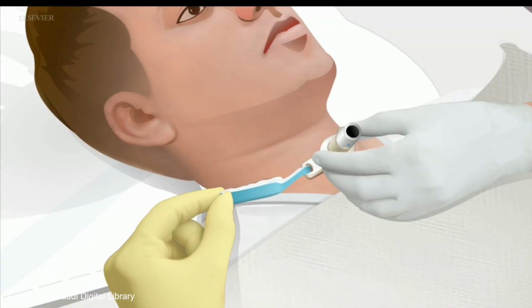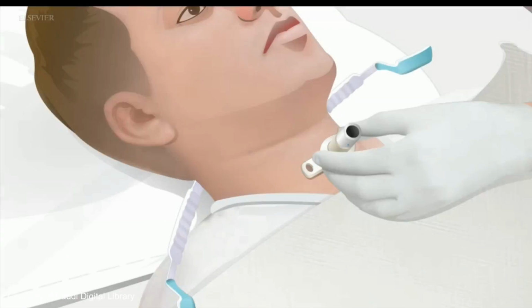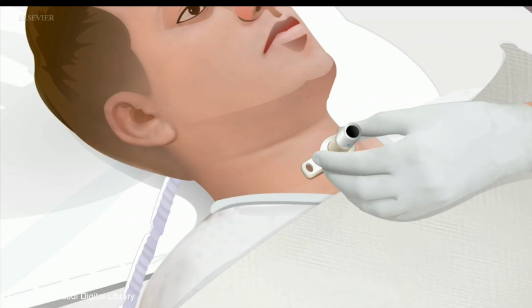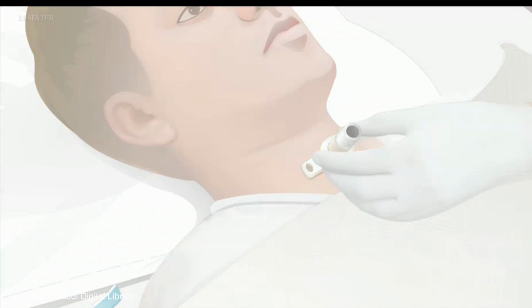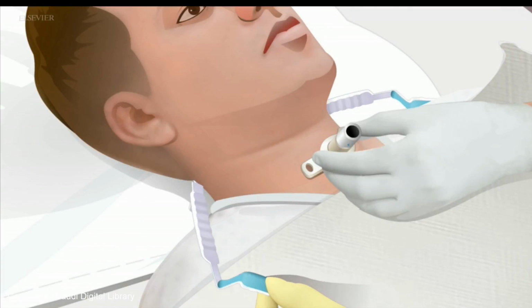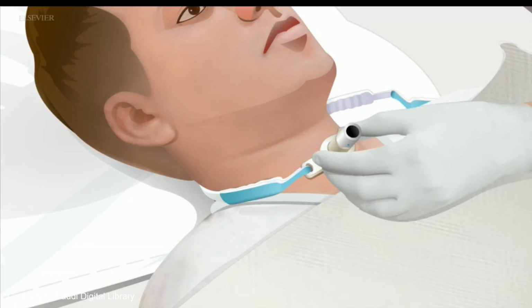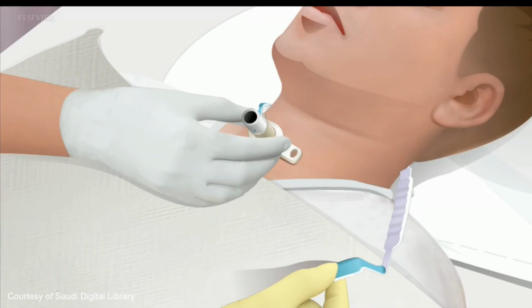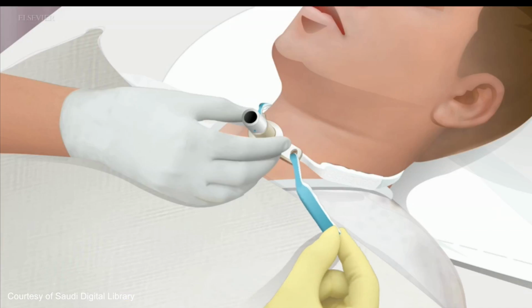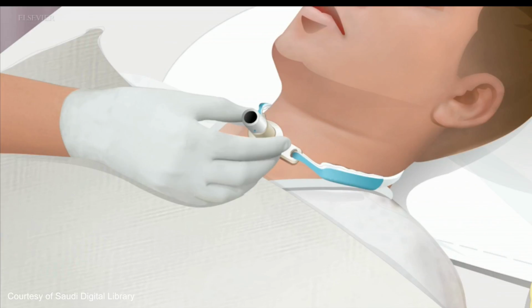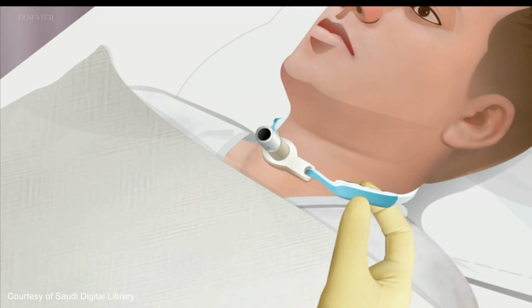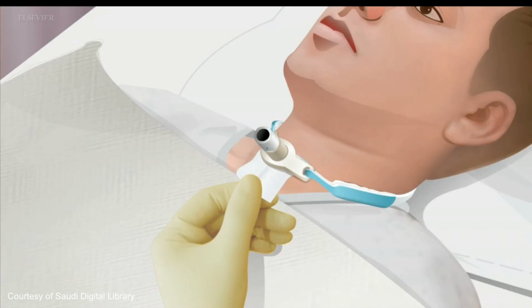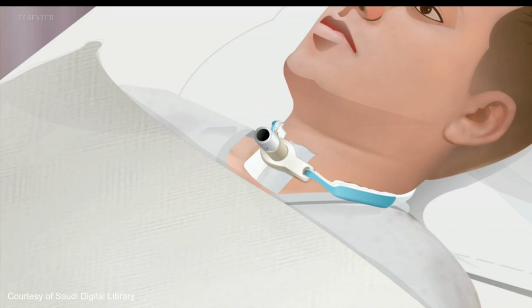Secure tube, tracheostomy tube holder. Instruct the assistant, if available, to don gloves and securely hold the tracheostomy tube in place. Align the strap under the patient's neck. Be sure that the hook and loop fastener attachments are on either side of the tracheostomy tube. Place the narrow end of the ties under and through the faceplate eyelets. Pull the ends even and secure with hook and loop fastener closures. Verify that there is space for only one loose or two snug finger widths under the neck strap.